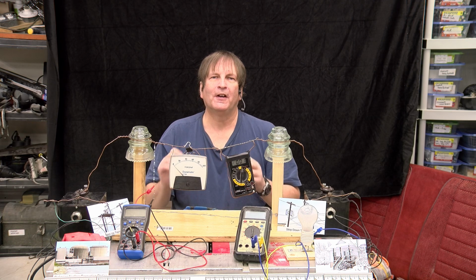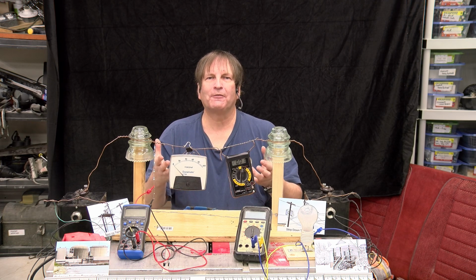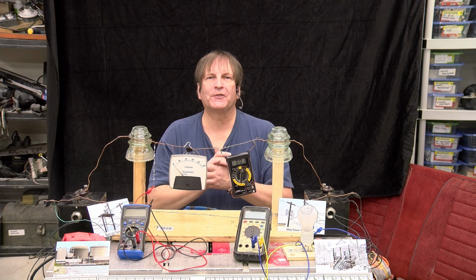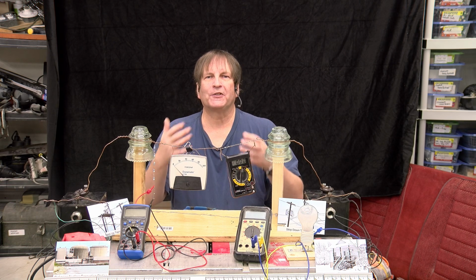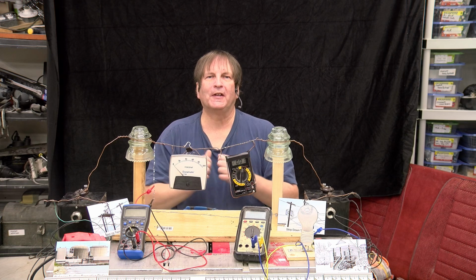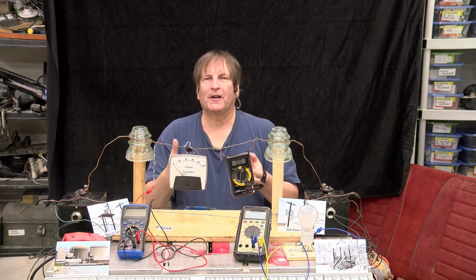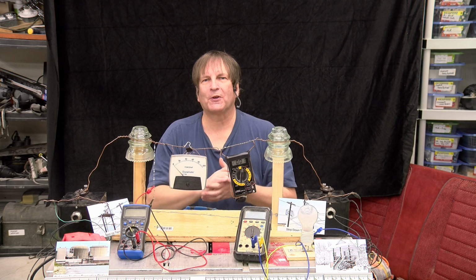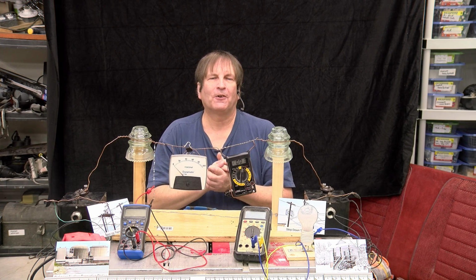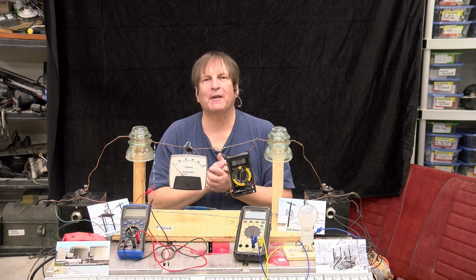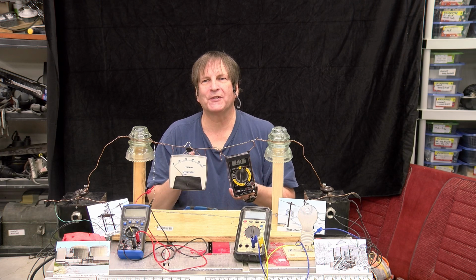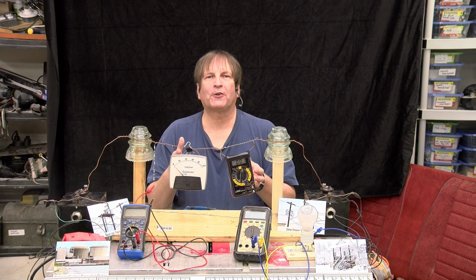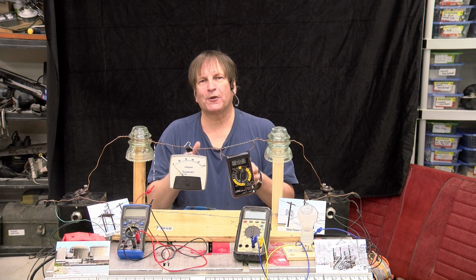The other effect that we have to take account for is something called the skin depth. And essentially what skin depth is a result of the frequency of the power. In our case, 60 hertz, in other parts of the world, 50 hertz. And for 50 or 60 hertz, the skin depth is somewhere around 1 centimeter, give or take. And what that means is the bulk of the electricity flows on the outer 1 centimeter of the electrical conductor.